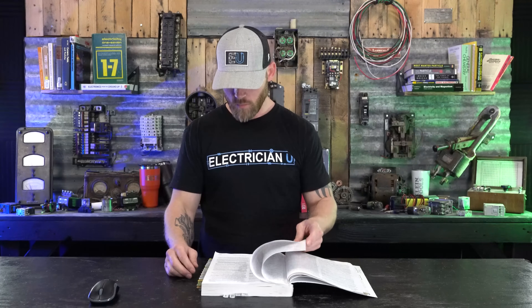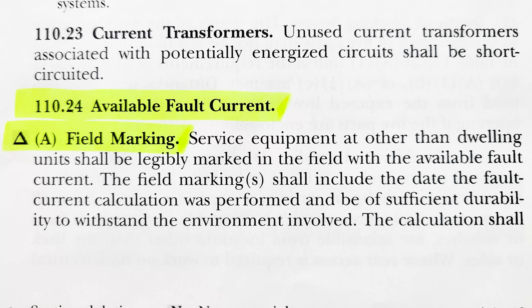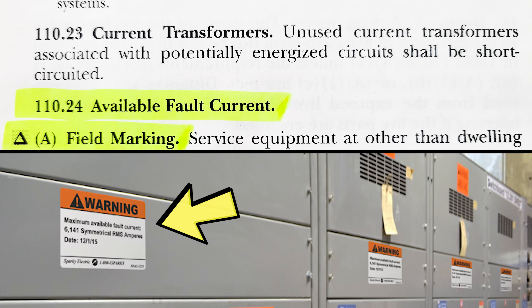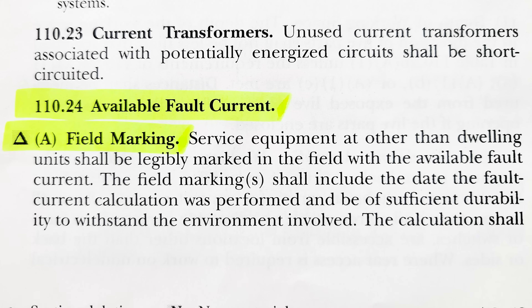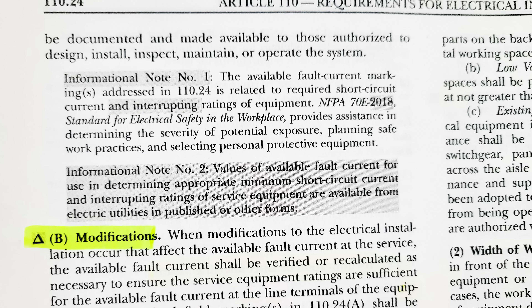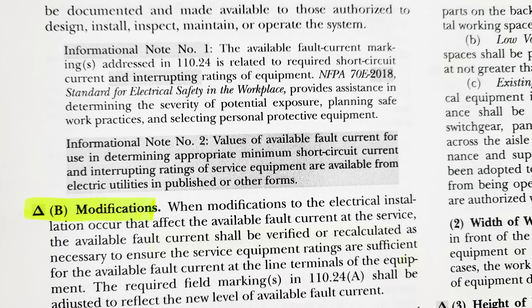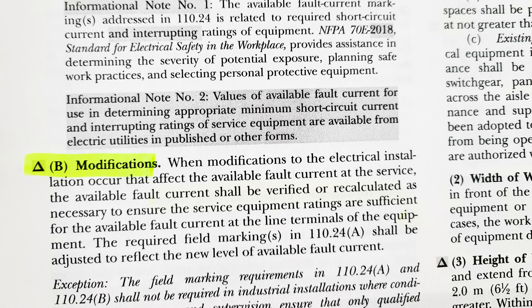NEC 110.24 covers available fault current and field marking of panels. Section 110.24(A) states that service equipment at other than dwellings shall be legibly marked in the field with the available fault current. The marking must include the date the calculation was performed and be of sufficient durability for the environment. The calculation shall be documented and made available to those authorized to design, install, inspect, maintain, and operate the system. Section (B) requires that any modifications to the service also require updating the AFC calculation and date.